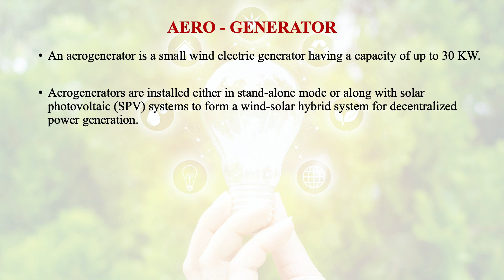Then comes the aerogenerator. An aerogenerator is a small wind electric generator having a capacity of up to 30 kW. These are generally installed either in standalone mode or along with a solar photovoltaic system to form a wind-solar hybrid system for decentralized power generation. These are suitable for power generation in unelectrified areas having adequate wind speeds, and generally the rotor of these kinds of aerogenerators is of 1 to 10 meter diameter, having 2 to 3 blades, permanent magnet generator, control devices, yaw mechanism, tower, storage battery, etc.